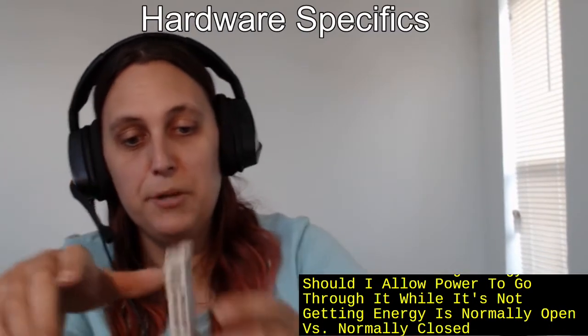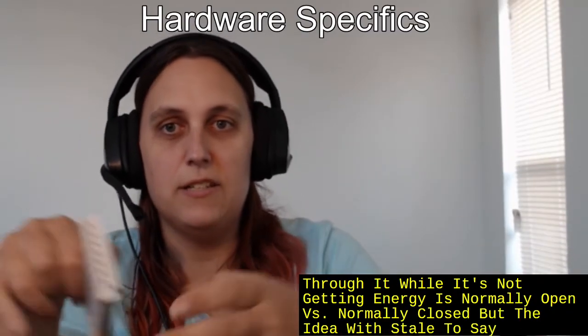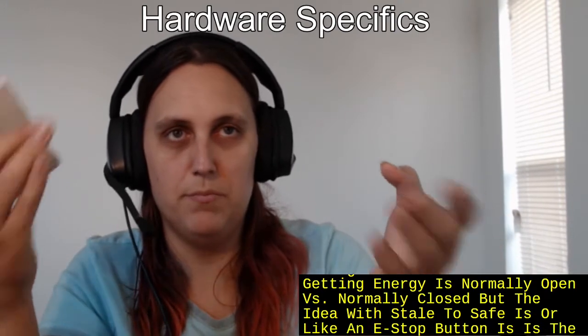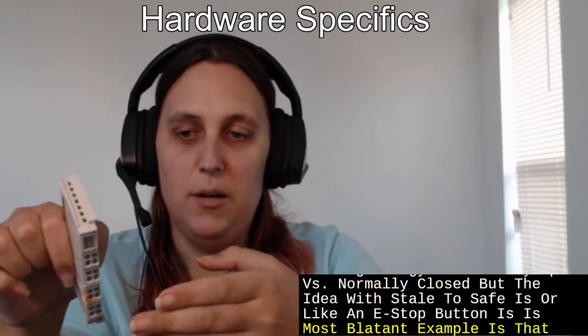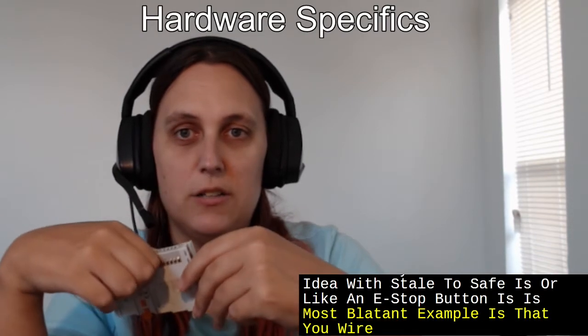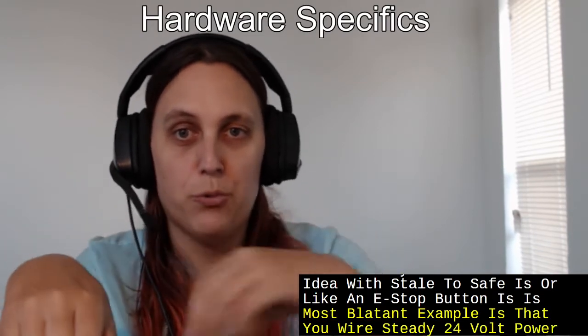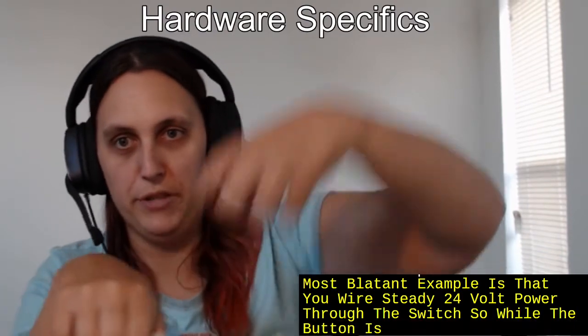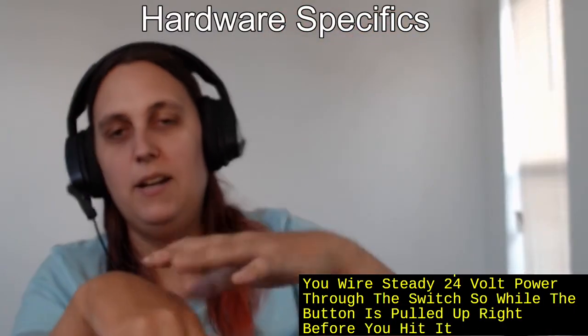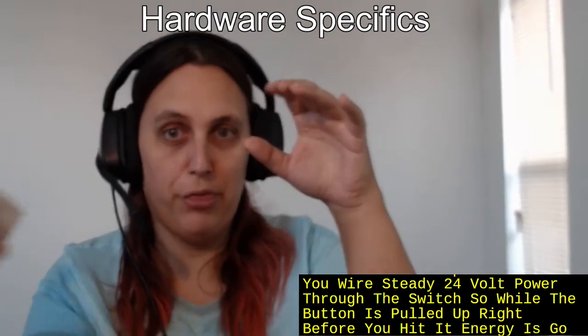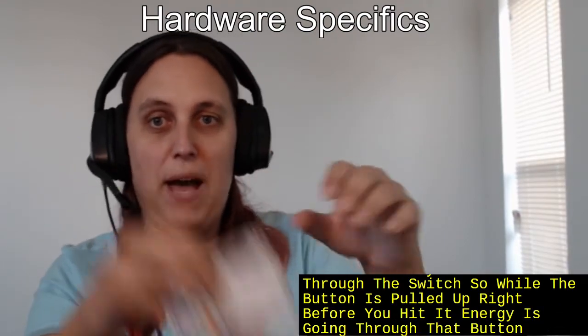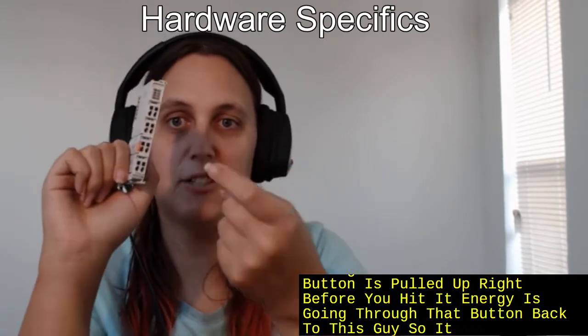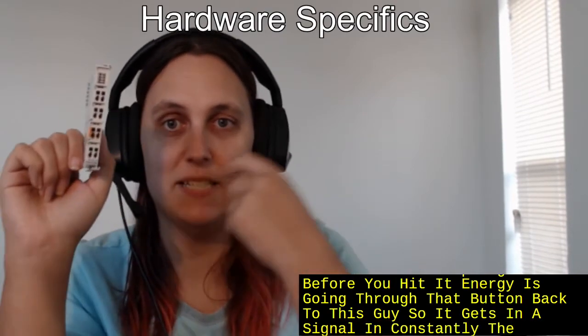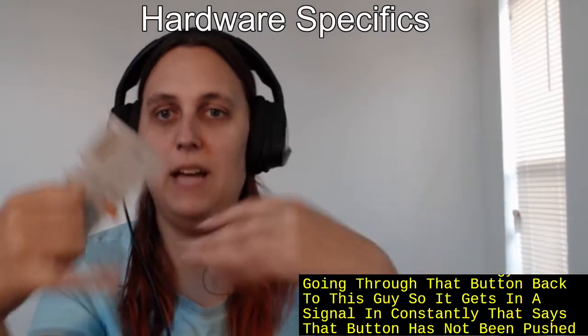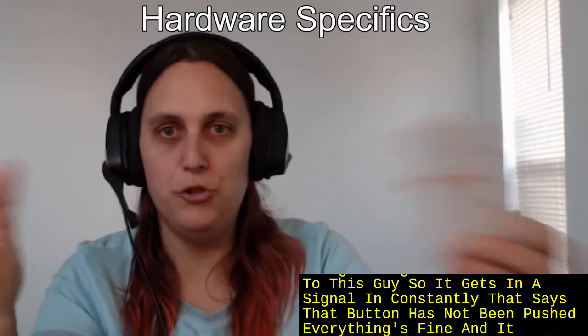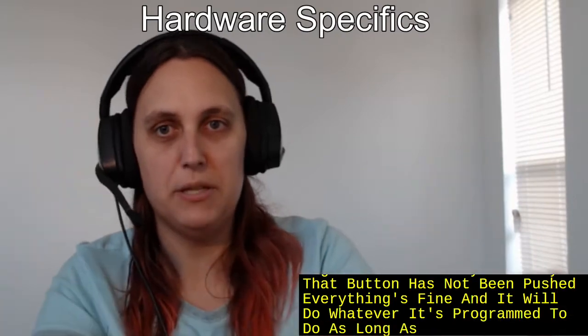But the idea with fail to safe, and an e-stop button is the most blatant example, is that you wire steady 24-volt power through the switch. So while the button is pulled up, right before you hit it, energy is going through that button back to this guy. So it gets a signal in constantly that says that button has not been pushed. Everything's fine. And it will do whatever it's programmed to do as long as that button's not pushed.